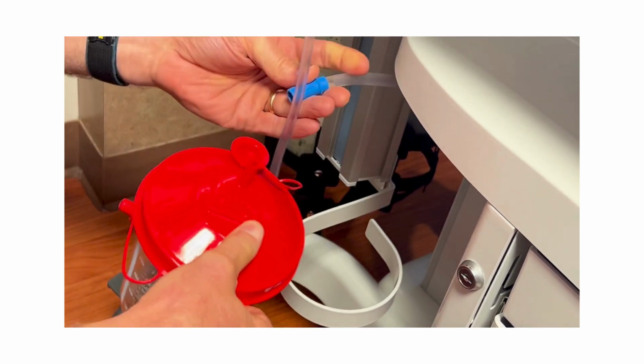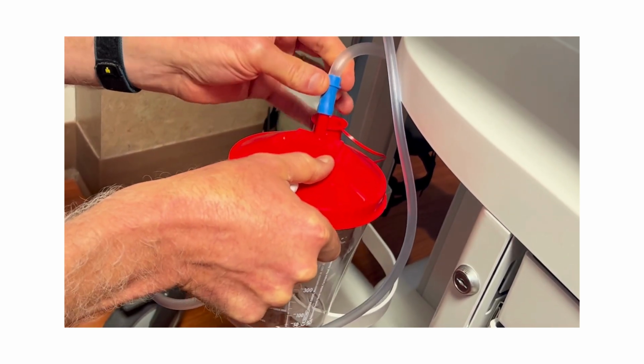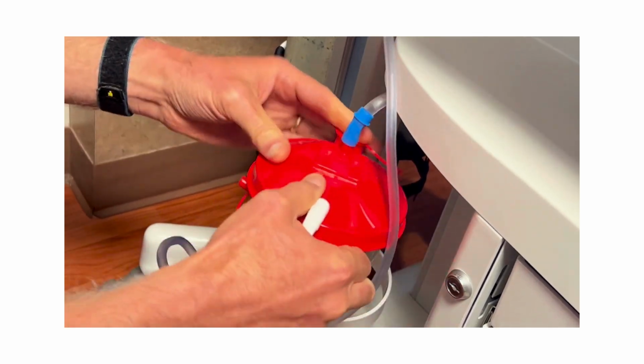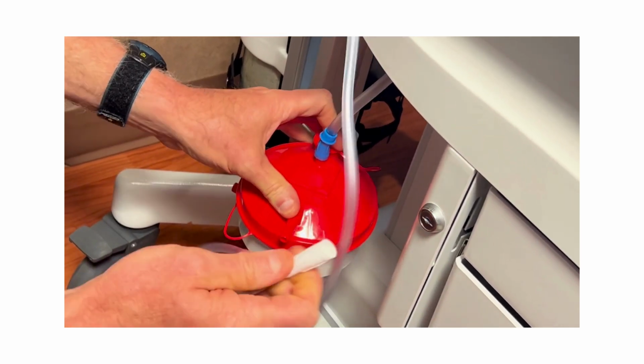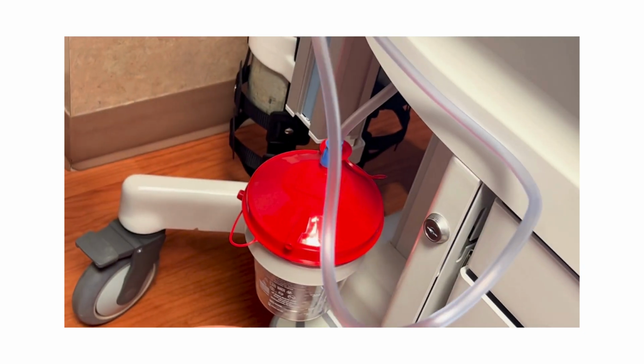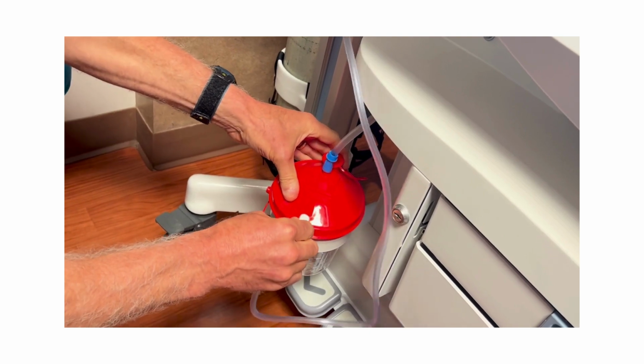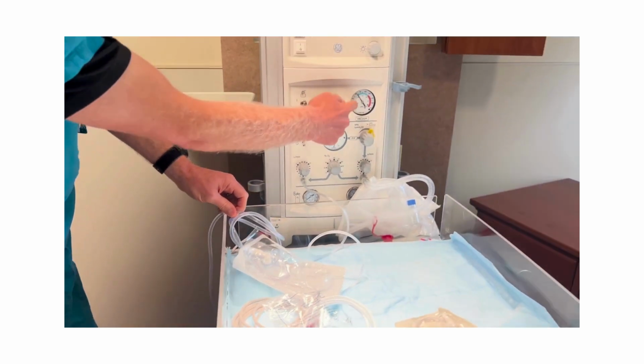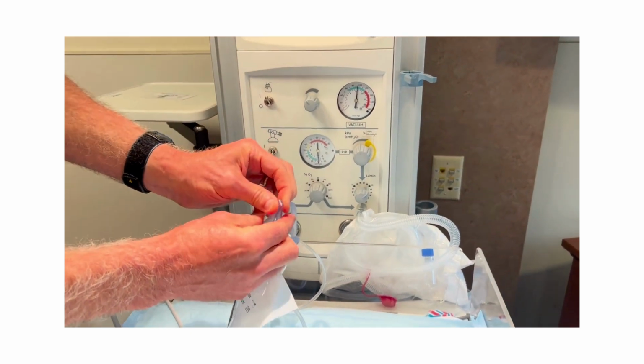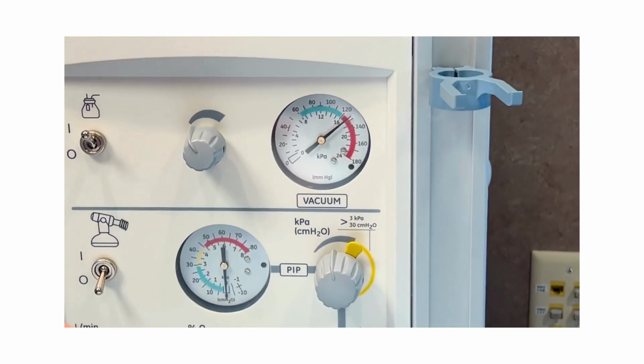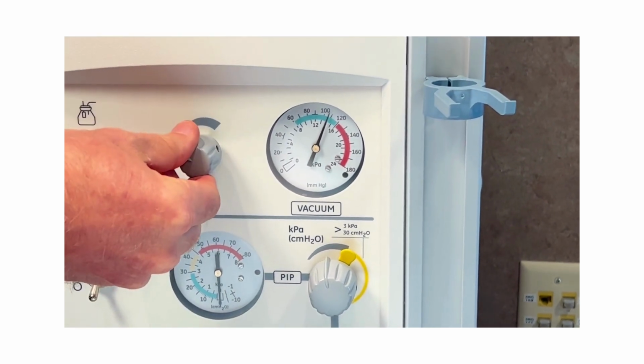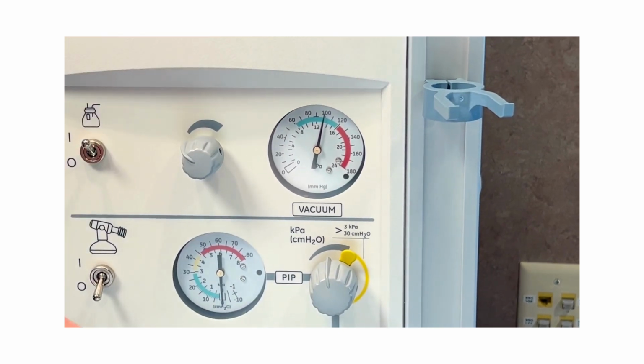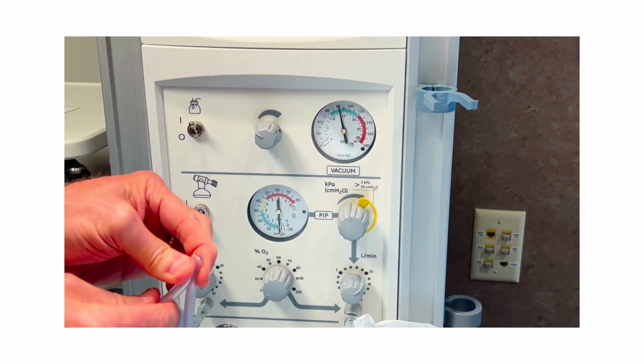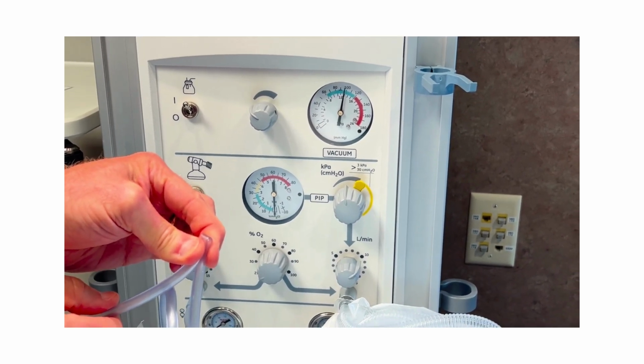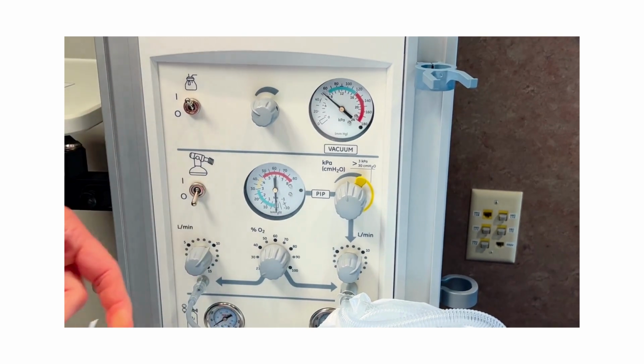So the top is for the bed vacuum to go hook onto, provide suction. And then the bottom one is just your tubing that you get from your supply room, wherever, to plug in here. And then you want to check your pressures with your manometer here. So you just kink it off and make sure you're at the right pressure. That's too high, so we would turn that down. There's 100. So you can let go and then test it again, block it off, and there it goes to 100. So anywhere 80 to 100, and then you have your suction pressure set.